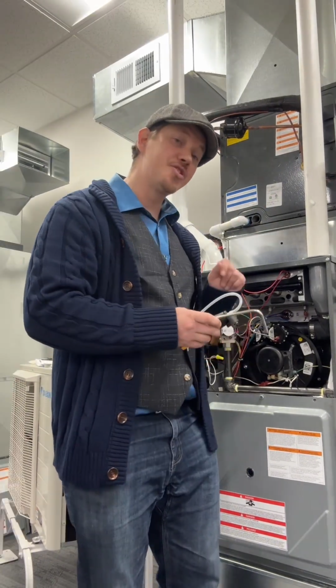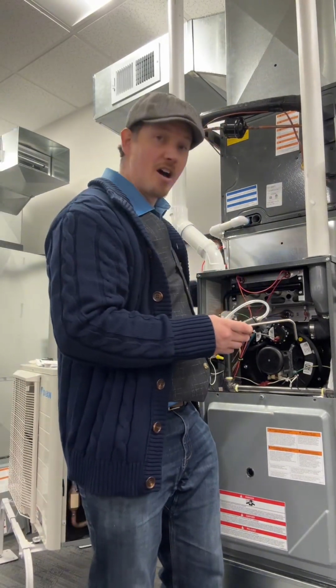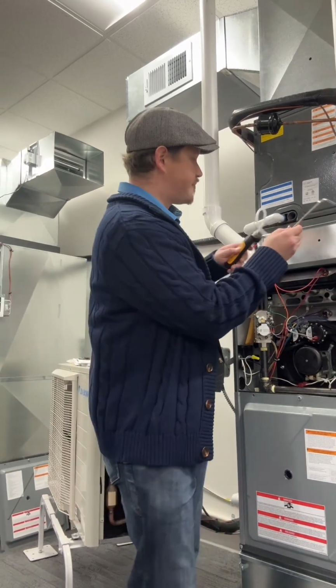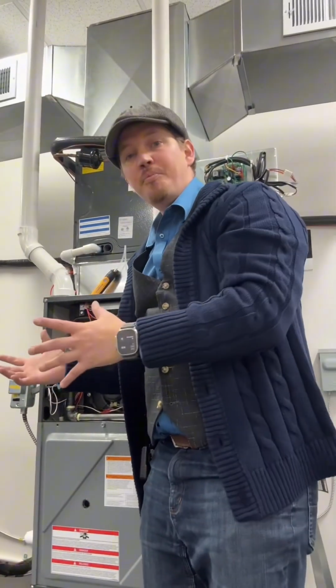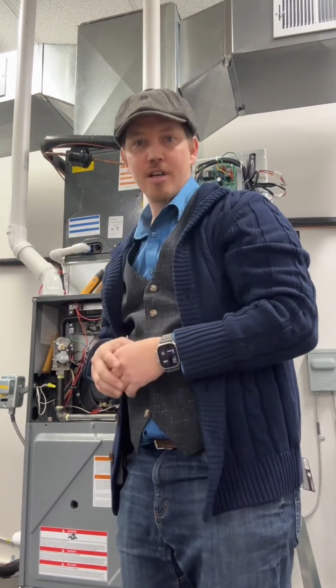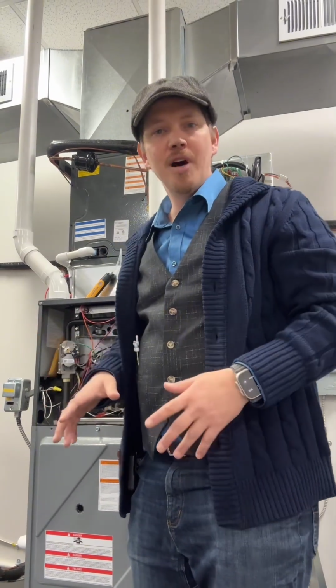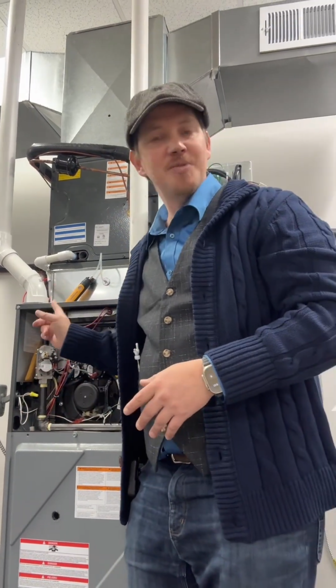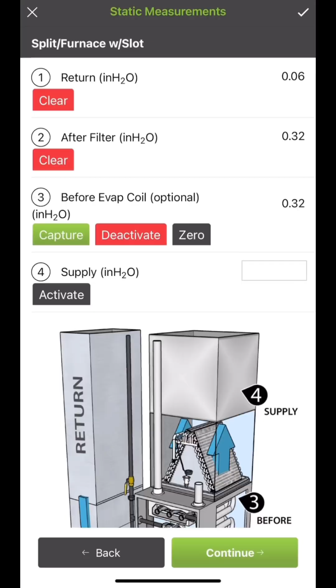You may have to install a test port somewhere on the side, but I'm trying to push air through this coil and ductwork. How much is that getting restricted? And that's what this reading is getting. So now I catch that reading.